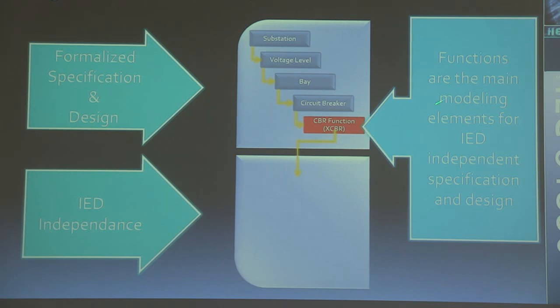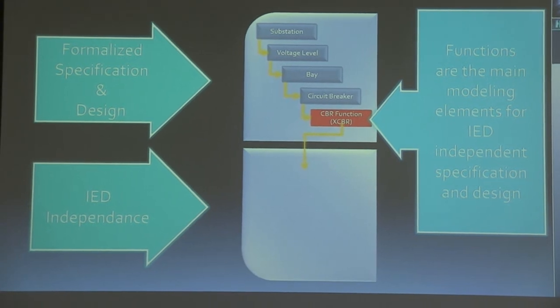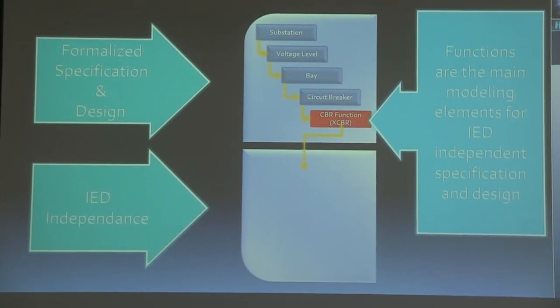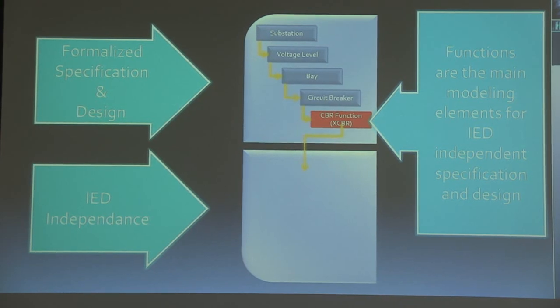process element which allows us to allocate several substations in one process, which allows us to describe power lines between the substations. So we can today model in a device-independent way our power system completely in 61850. It is very close to CIM. The difference is here we are really focusing on the logical nodes at the end.